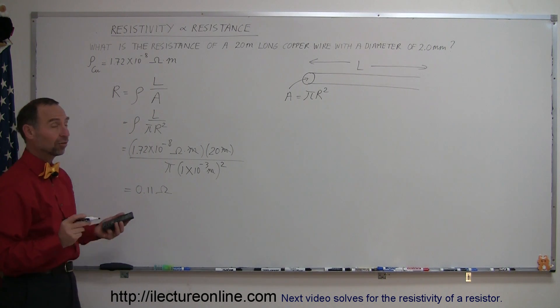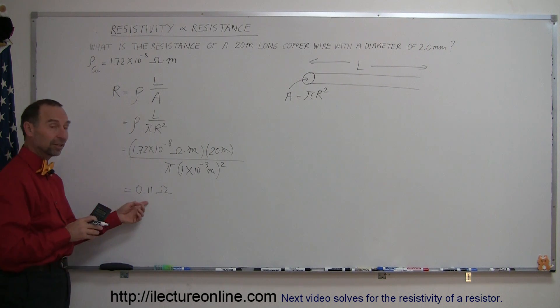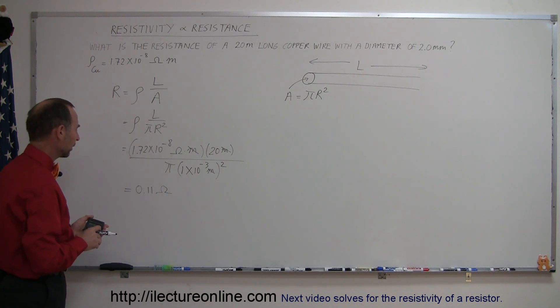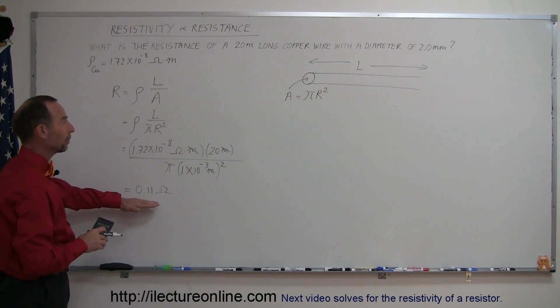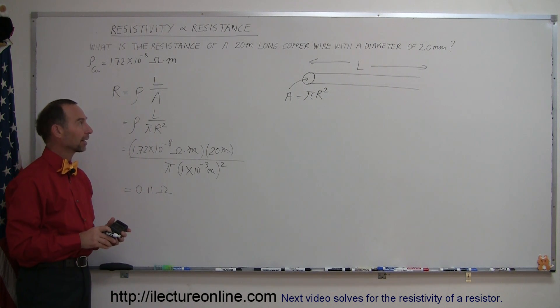You can see that the resistance of a 20 meter long wire, even though it's made out of copper, is not necessarily insignificant compared to devices that we connect to the wire. This is probably relatively small, but it cannot be neglected. We do know that we have some power loss in electrical wiring.